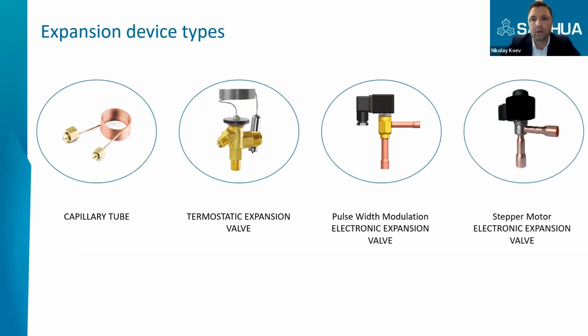Here I will show you two types of electronic expansion valves: pulse-width modulation and stepper motor electronic expansion valves. The electronic expansion valves cannot operate independently, so a controller is needed in order to measure the pressure and the temperature at the outlet of the evaporator and to regulate the superheat by adjusting the position of the electronic expansion valve. What's the difference between these two types? The pulse-width modulation valve works similarly to a solenoid valve, so it is either closed or open. Here we don't have continuous modulation of the refrigerant flow, so it is either 100% or zero.